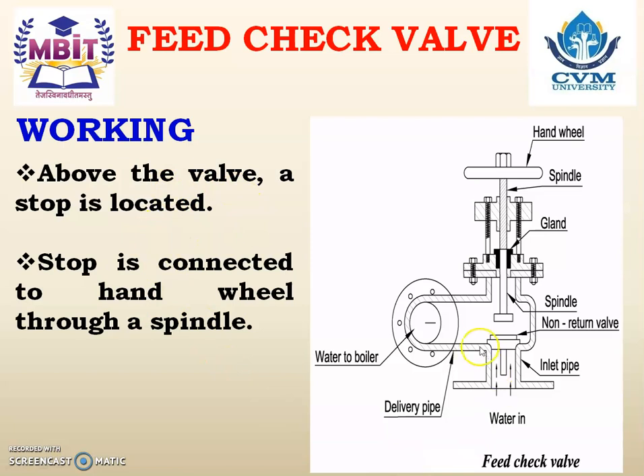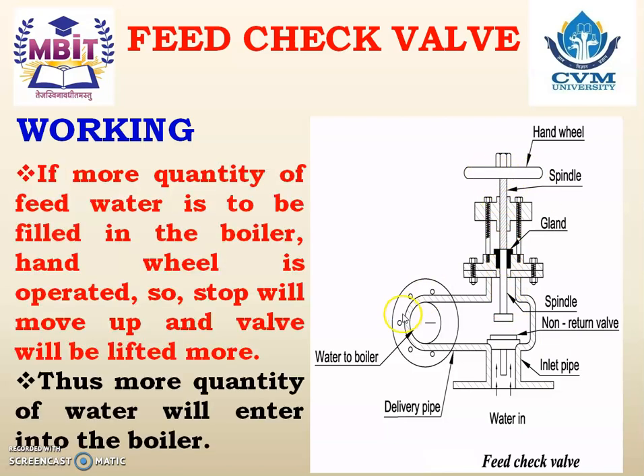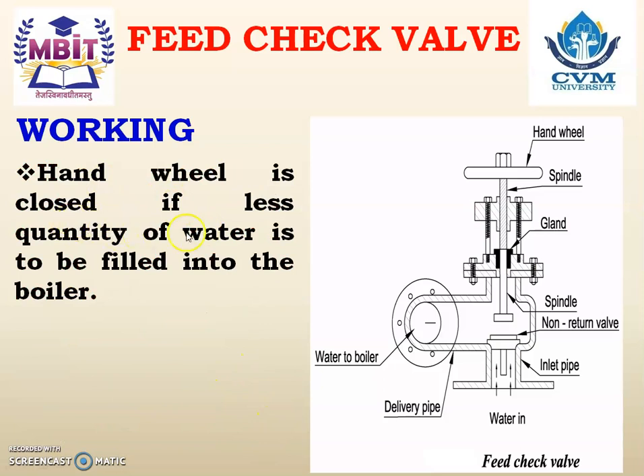Above the valve, a stop is located, connected to a hand wheel through a spindle. If more quantity of feed water is to be filled inside the boiler, the hand wheel is operated, causing the stop to move up and the valve to be lifted more — the stop decides the operating range of the non-return valve. If the hand wheel is operated and the stop moves up, more water enters the boiler. The hand wheel is closed if less quantity of water is to be filled.